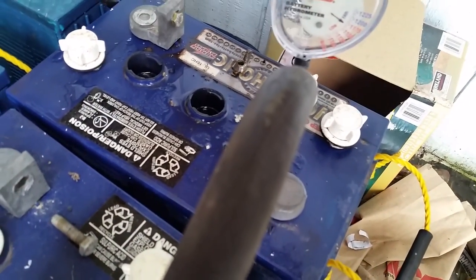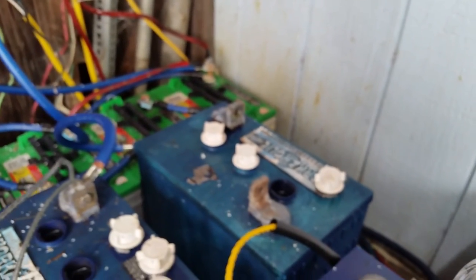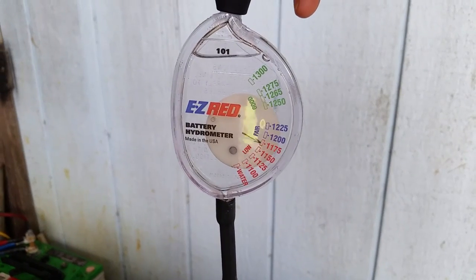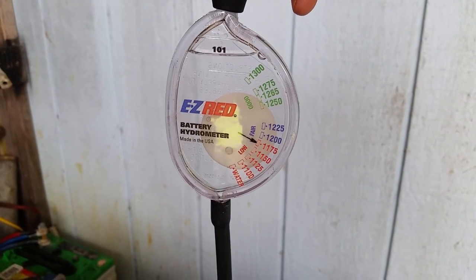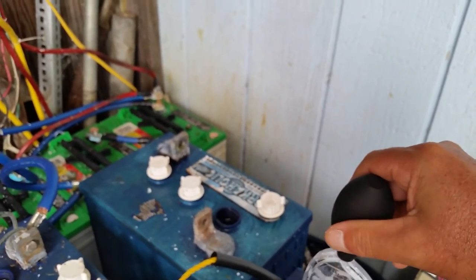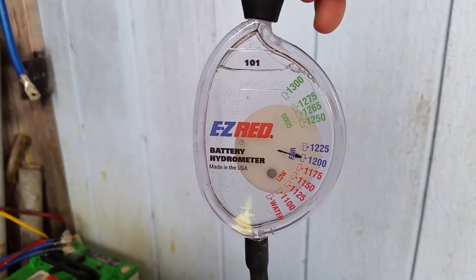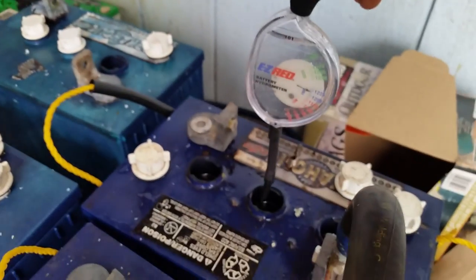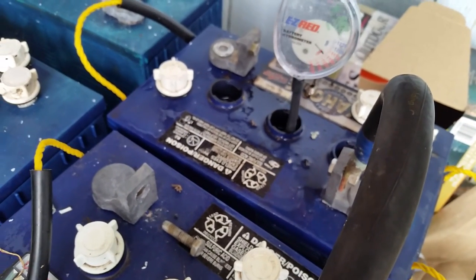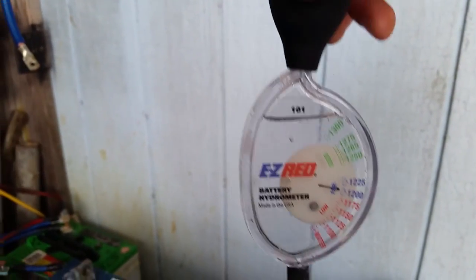Let's go back to these other batteries and double-check our numbers. Let's pull up — this one is saying 'fair' at 1200. Next cell: the first cell was at 1200, now this one's at 1175, so you can see it's going down a little between cells — they're not going to be the same all the way across the board because you may have a shorted cell within the battery. Now the last cell is back up to 1200.